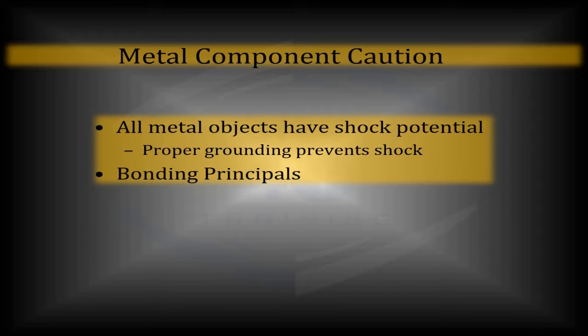All metal objects have that shock potential. Proper grounding is going to prevent that shock potential. And when it comes to bonding principles, I'm going to defer that to NFPA 54 section 7.13.2 when dealing with CSST. It's very important that you remember that. NFPA 54 section 7.13.2, in which it says CSST, corrugated stainless steel tubing, gas tight, TracPipe, diamond pipe, things like that. Any length of CSST has to be bonded, beginning with the first downstream fitting from the source to the first fitting on the length of CSST.